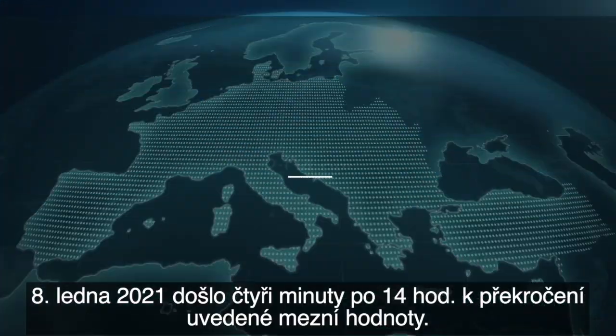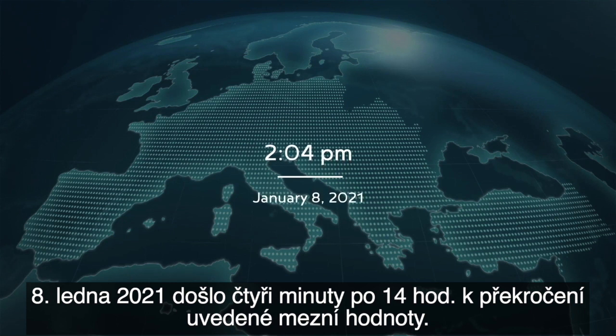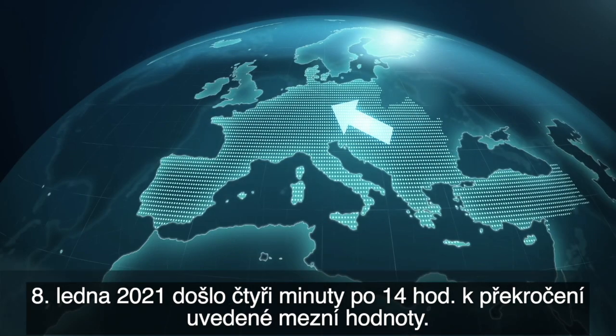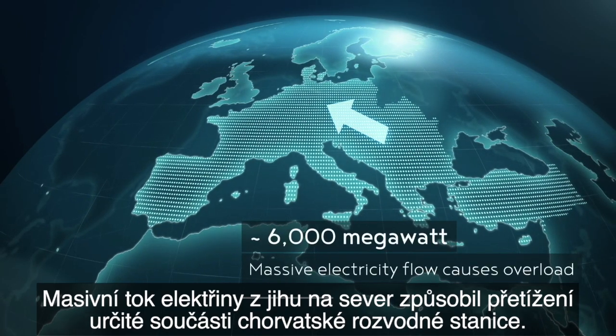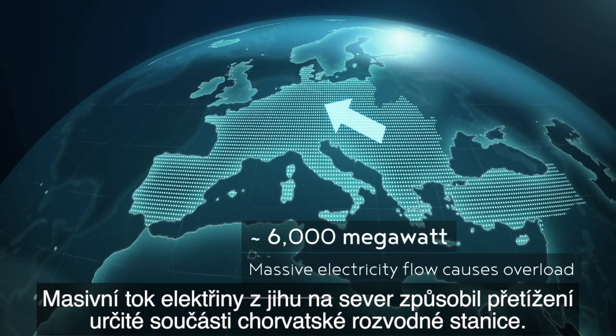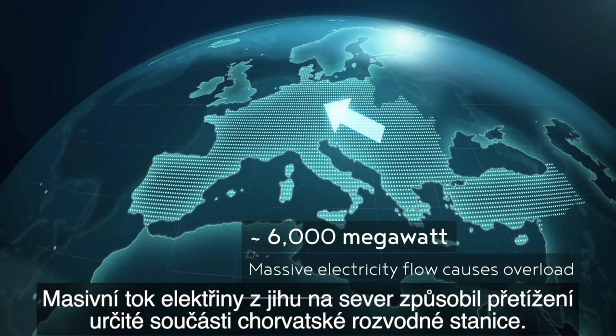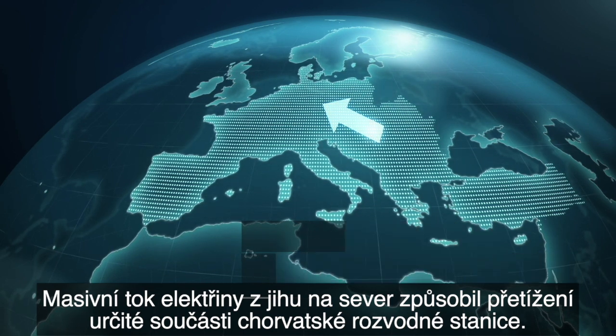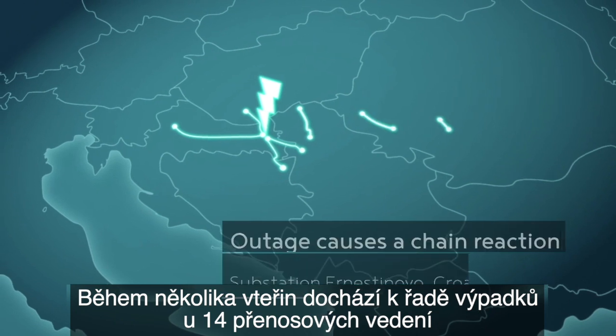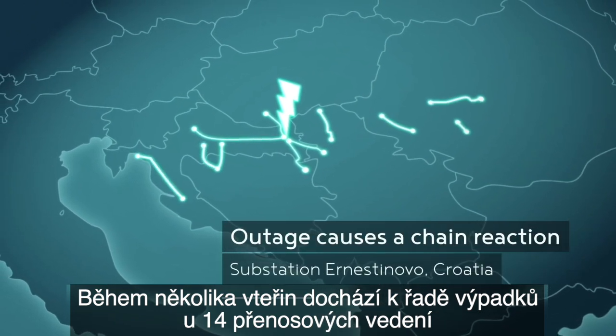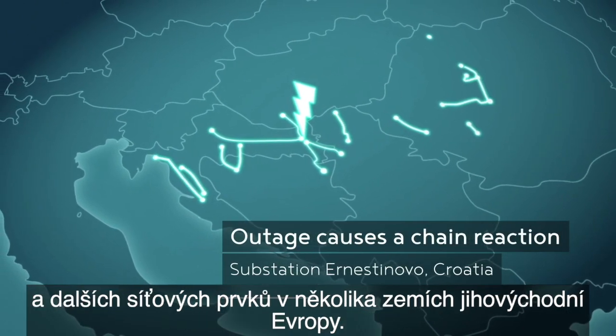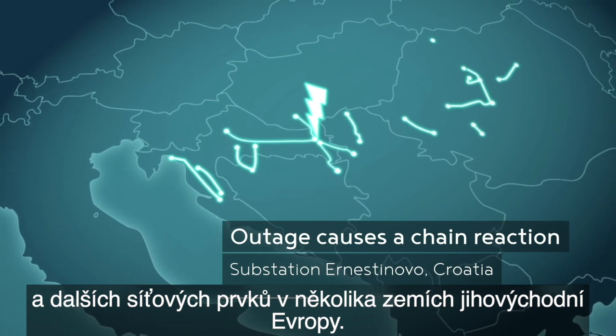On the 8th of January 2021, at 4 minutes past 2 p.m., this threshold is clearly exceeded. A massive electricity flow from south to north causes an overload of a plant component in a Croatian substation. Within seconds, this leads to a sequence of outages of 14 transmission lines and other grid elements in several countries of southeastern Europe.